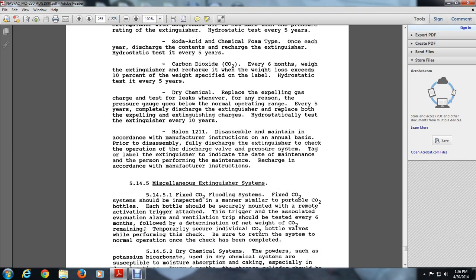5.14.5 miscellaneous extinguisher systems. 5.14.5.1 fixed carbon dioxide flooding system. Fixed carbon dioxide systems should be inspected in a manner similar to portable carbon dioxide bottles. Each bottle should be securely mounted, with the remote activation trigger attached.